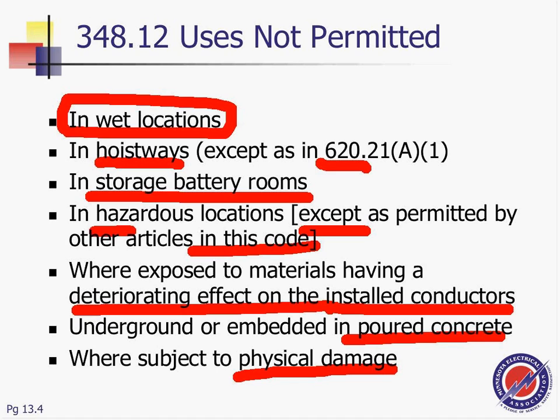If you have physical damage, believe it or not, well, why don't you go put your flexible metallic conduit in a rigid? Does that sound weird? Putting a flexible metallic conduit in a rigid conduit, you might as well just get rid of it all together. So if it's subject to physical damage, then you cannot use it. As you can see, guys, about the use, it's really limitations. The main limitation is really wet location, guys. Wet location is the main limitation of that baby. The main limitation.